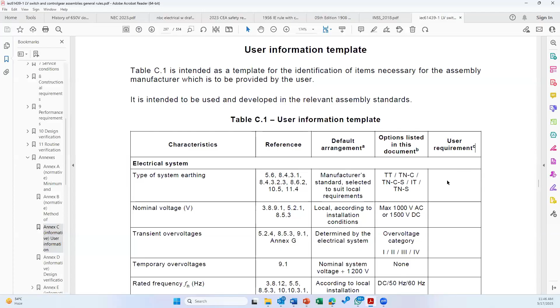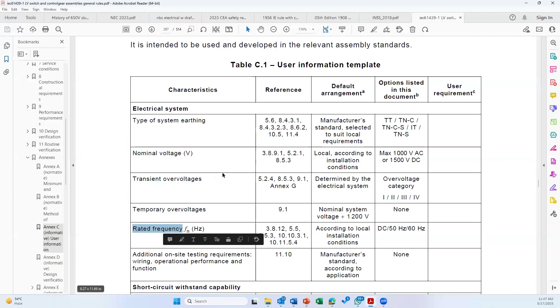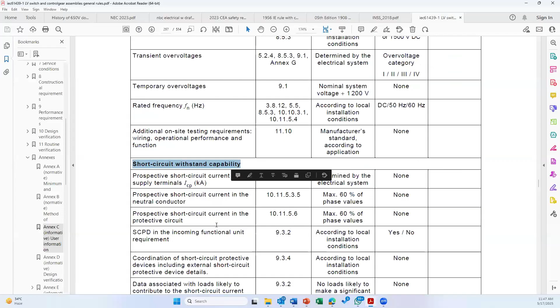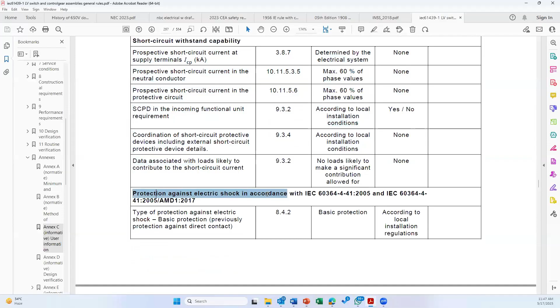Now you see it starts with electrical system. Type of system earthing. You can see here TT, TNC, TNCS, IT, TNS, different system earthing are there. The panel board design, the selection of the device, or sometimes the setting of the parameters of the assembly depends upon the kind of system earthing. Then it goes to nominal voltage, transient overvoltage, temporary overvoltage, rated frequency, additional site testing requirement. Number 2, the short circuit withstand capabilities, which starts with sub requirements of about 5. Protection against electric shock, how you are achieving it, is again subsection 2. Installation, the environment has to be specified.